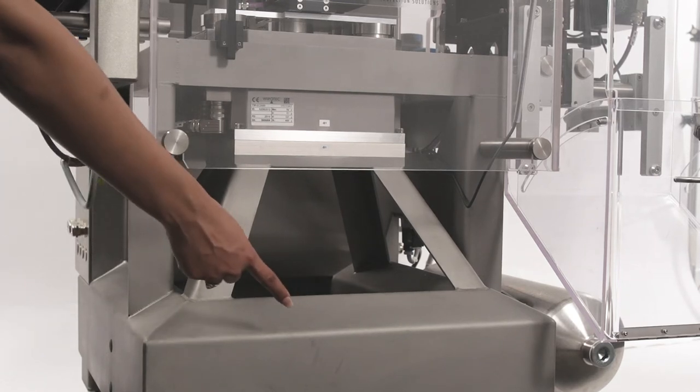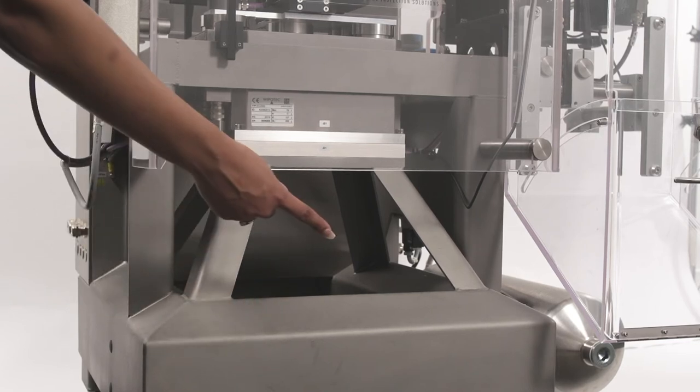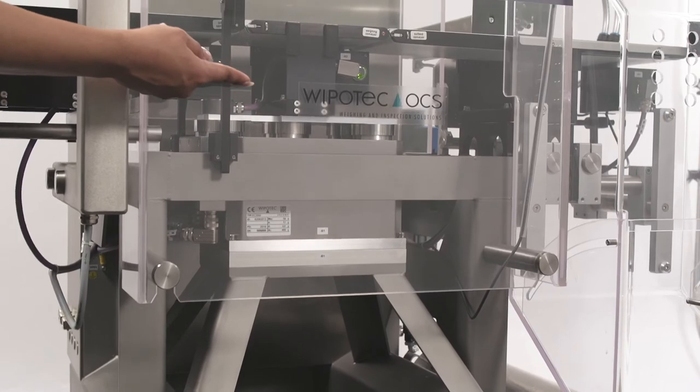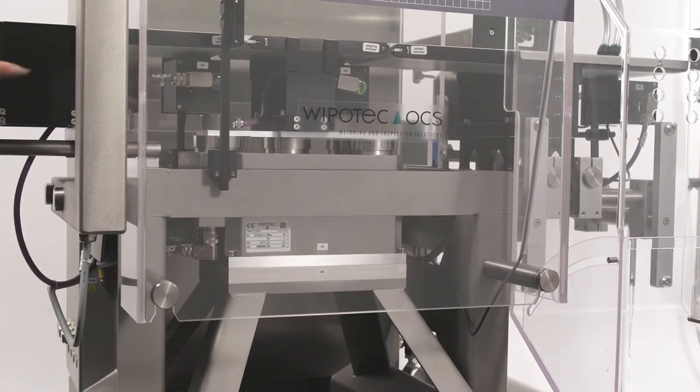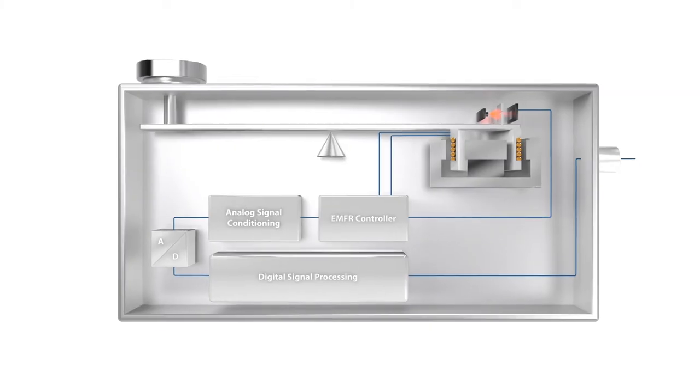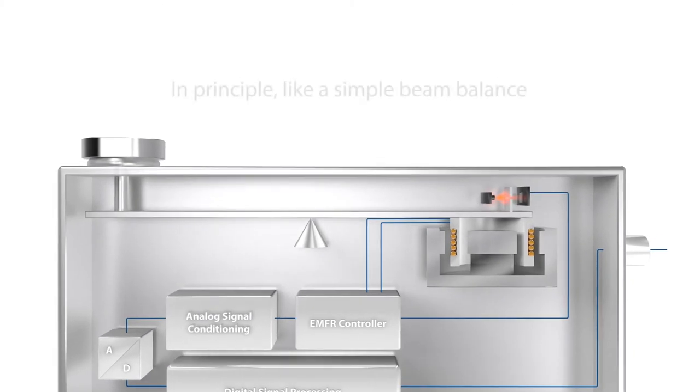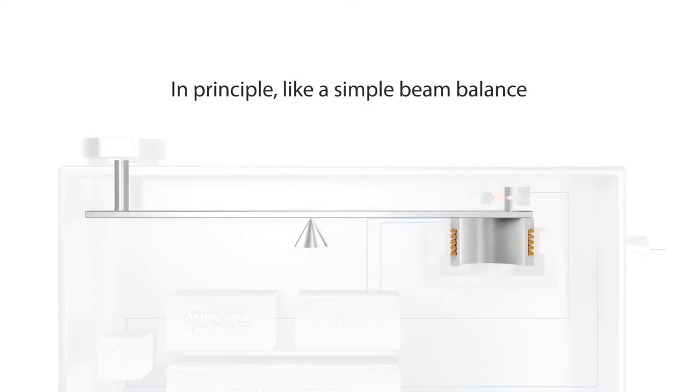The base of the frame is filled with concrete to ensure stability, which in turn helps with precision product weighing. Moving up the center portion of the checkweigher, we come to the EMFR weigh cell. EMFR weigh cell technology is at the heart of all Wipotec OCS checkweighers. An EMFR weigh cell can be compared to a simple beam balance.